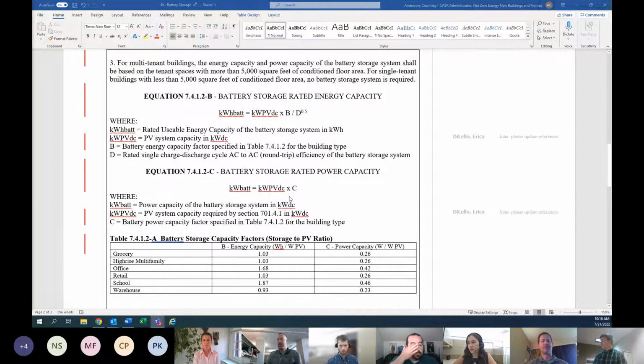So if you see down to Table A for the battery storage capacity factors, for example, for an office building, that 1.68 means that for every watt of PV, DC, that you have installed on the roof, you would have 1.68 watt-hours of battery storage available on site. These factors, or the sizing of the systems, were not designed to store every possible last watt of excess energy generated from the PV systems, but rather are used more for demand response, for shifting the energy loads, and to limit exports, such that the exported generation was no more than approximately 20% of the entire production of the system.